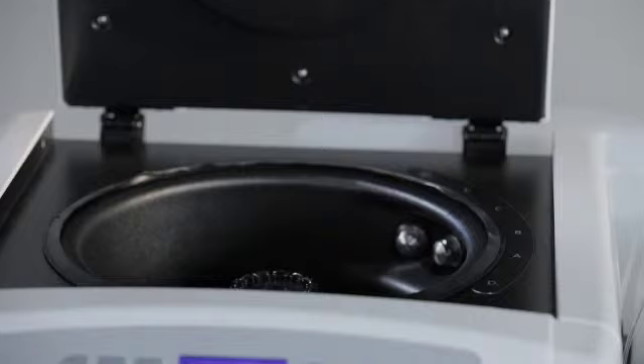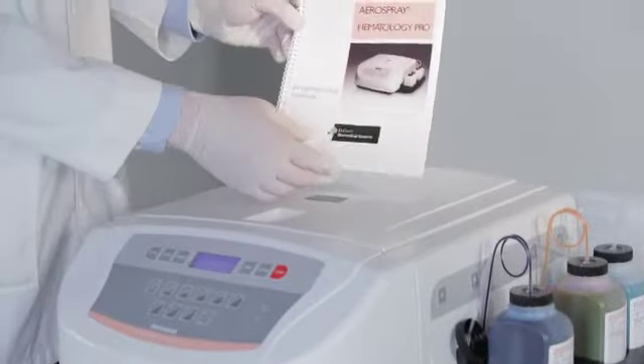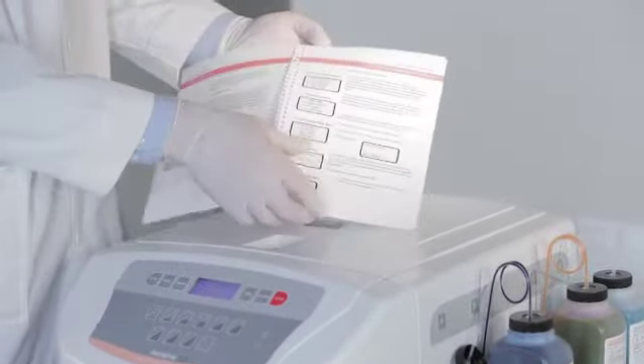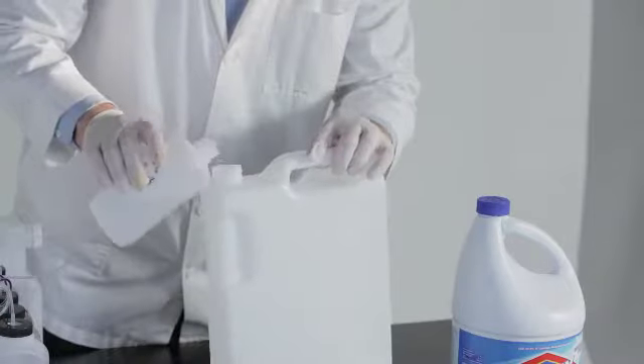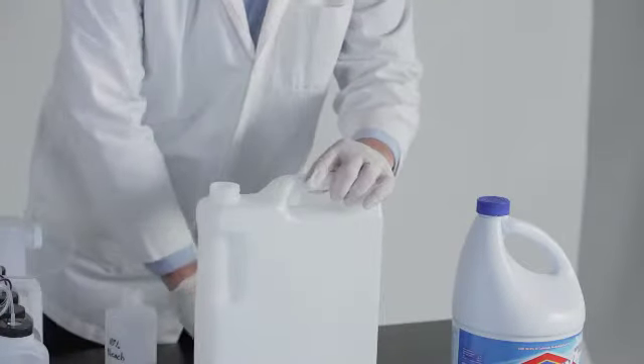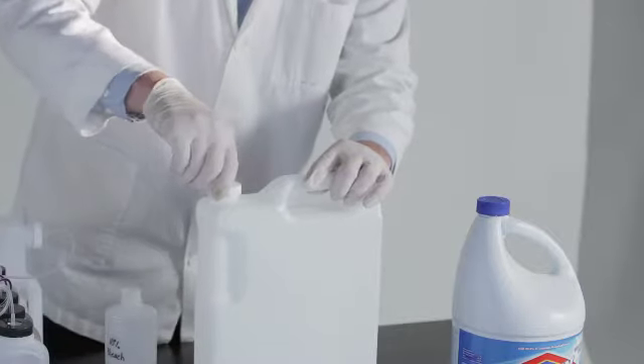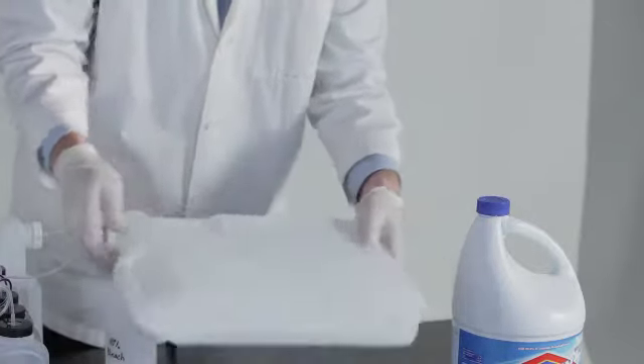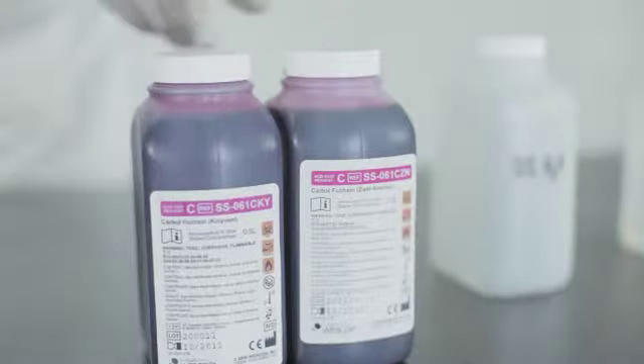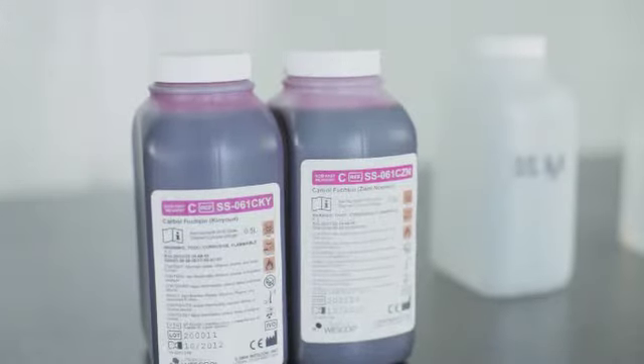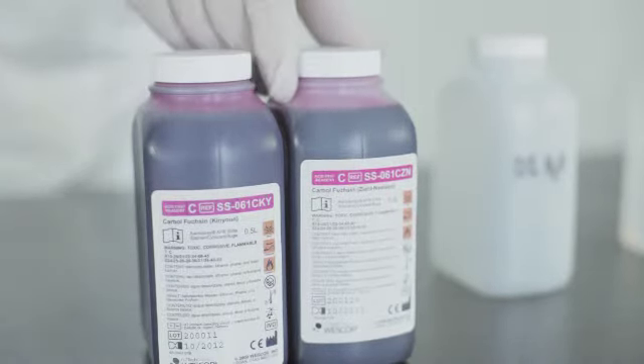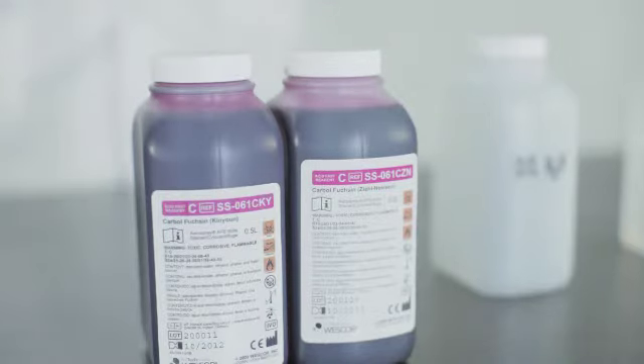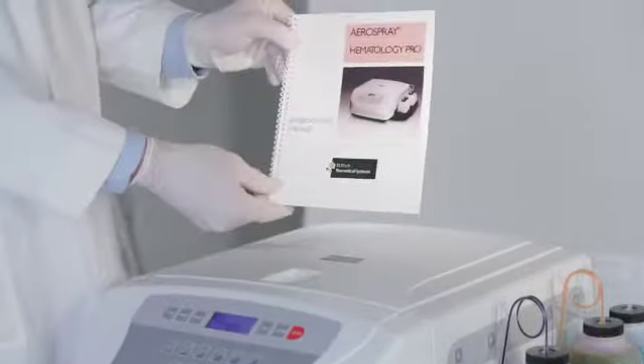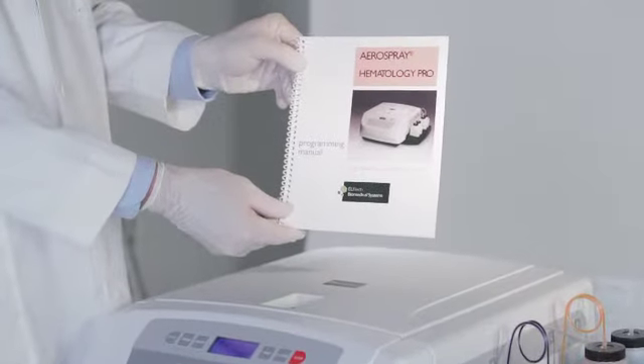A monthly B-line flush is also recommended for the B-line when potassium permanganate is being used. Instructions for performing the B-line flush are in the applications manual and the preventive maintenance chart. The flush is semi-automated with the firmware. The 5-liter container used on the D line should be cleaned with 10% bleach once per month to prevent bacterial contamination in the water. It is not recommended to switch between carbol fuchsin and fluorescent stains regularly. If users want a stainer to stain both carbol fuchsin and fluorescent stains, then they will need to have 2 stainers. Instructions for switching between the reagent sets are contained in the applications manual.